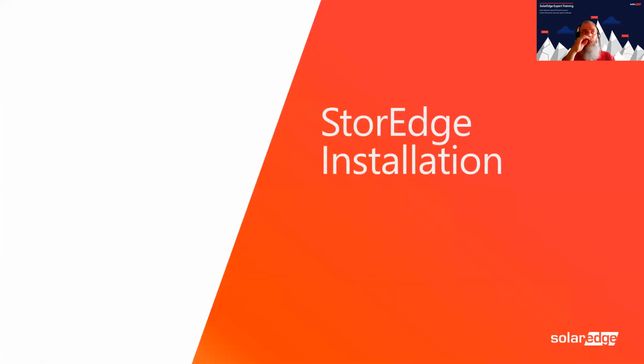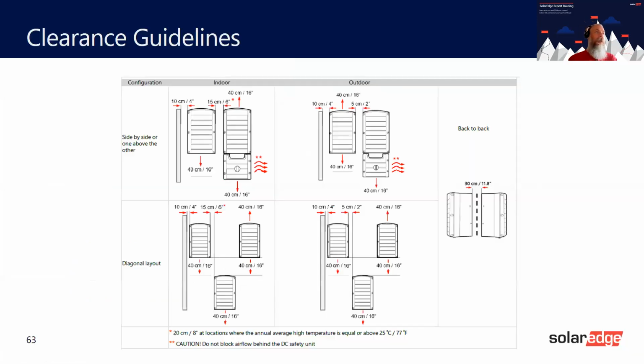So the installation, just some information for you. We have different spacings, indoor and outdoor. Indoor, we have a larger spacing, and that's because of the ambient temperature. It says here 20 centimeters if the ambient temperature is higher than 25 degrees. So depending where you're installing the inverter, you might have to move them away slightly. And then you've got airflow here. Do not block airflow behind the DC safety unit. So around here, please make sure you allow the same space as you do to the top of the inverter.